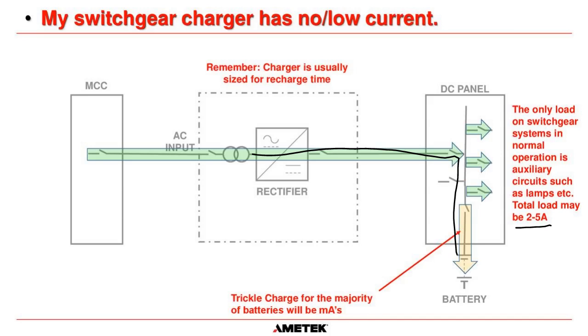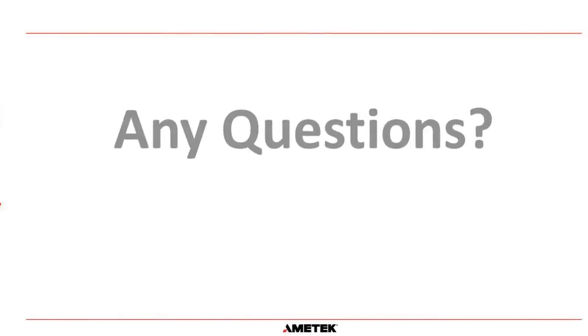So if you see low current on a switchgear system, it is not a big issue. It's not saying something is wrong. Basically, as long as you have 135 volts and you see some current trickle charging the battery, then you know everything's good. If you have 135 volts, then you have the potential to do work on the load circuits. So don't worry about that.